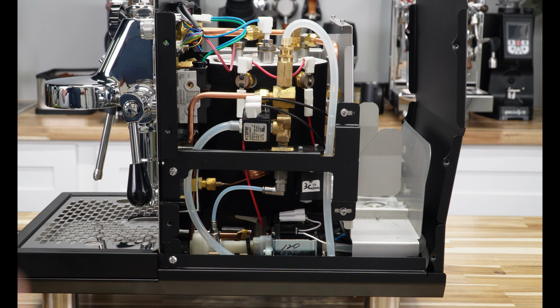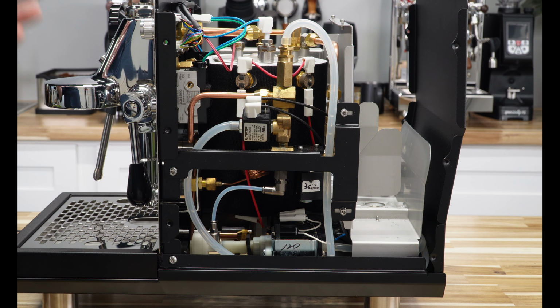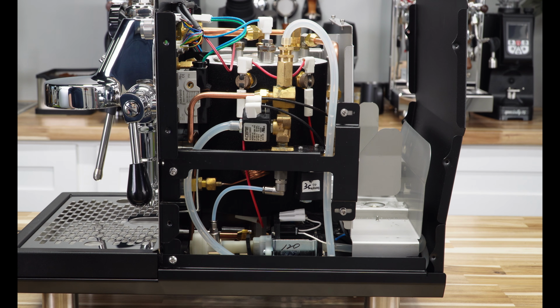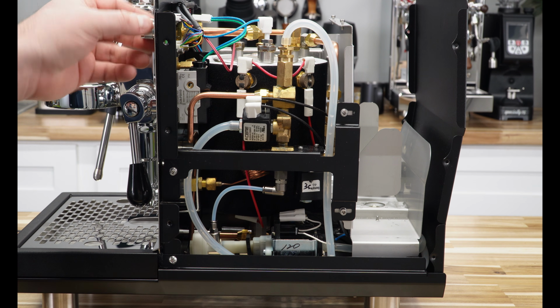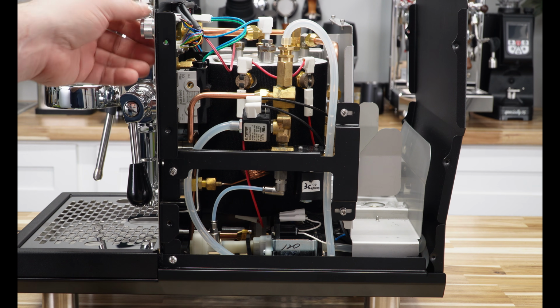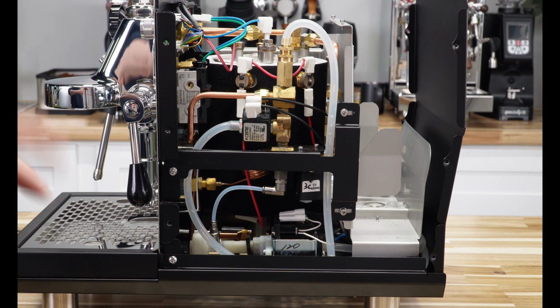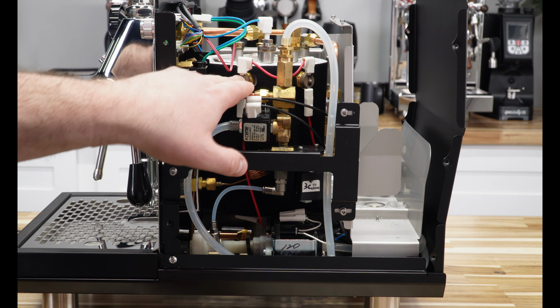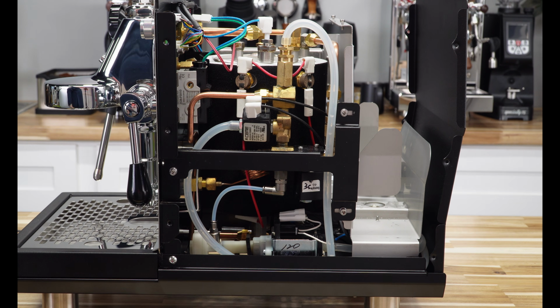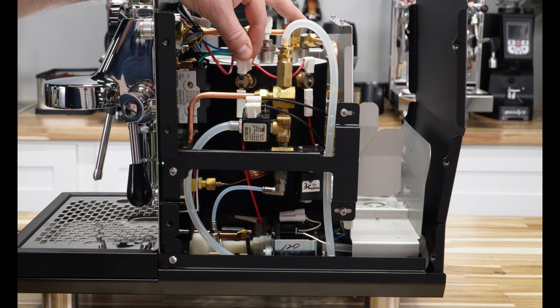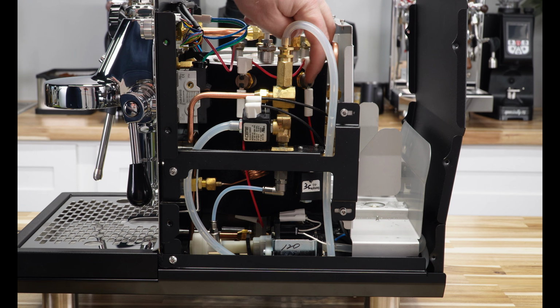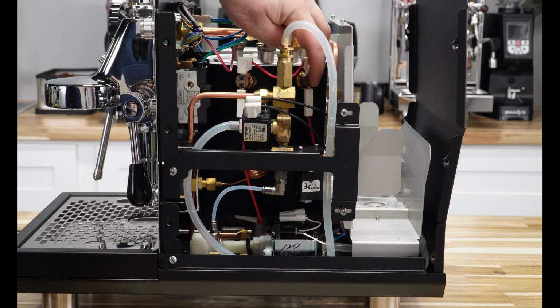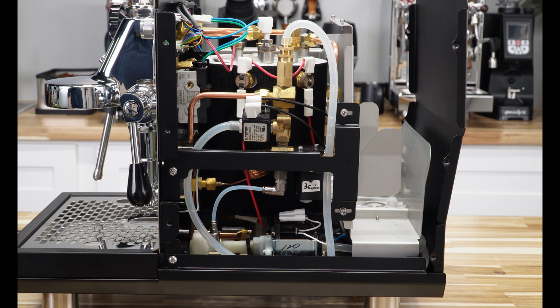Okay, so now we are on the right side of the machine. If you're looking from the front, you have the right side of the machine with the panel taken off. And at the top, you have your PID display. It's kind of hard to see at this angle, and your adjustment knob. For whatever reason, if one of those goes out, it's really easy to work on. Here are your thermal overloads that I mentioned earlier. Usually one of them does not have a button, and one of them does. And this one back here has a little gray button. So if it's not heating up, I would make sure to press that in.